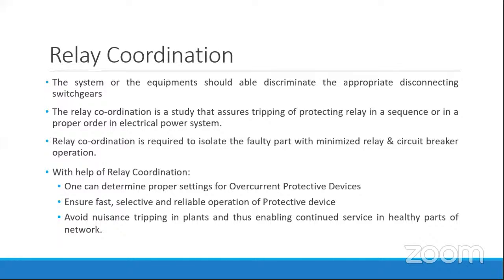With this relay coordination, we can ensure that faulty parts get isolated in a speedy manner, and that selective and reliable operation is ensured for normal conditions also. During normal conditions, the protective relay should be able to withstand the normal condition and detect the faulty condition, so that the normal condition is not interrupted or isolated, and is not detected as faulty. The relay coordination should be done in such a way as to avoid nuisance tripping in the plant, thus enabling continued service in the healthy part of the network.